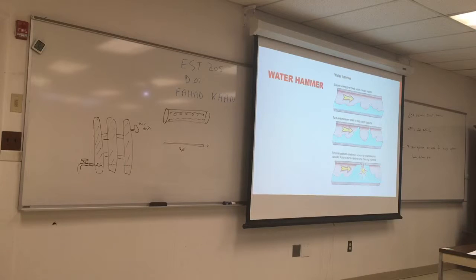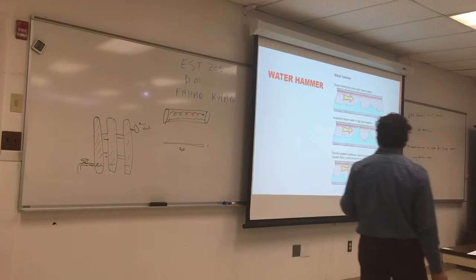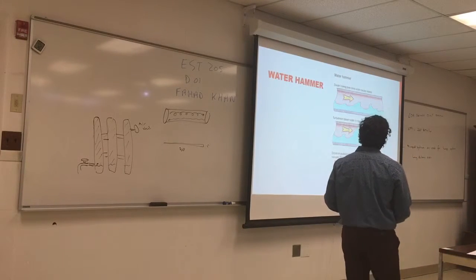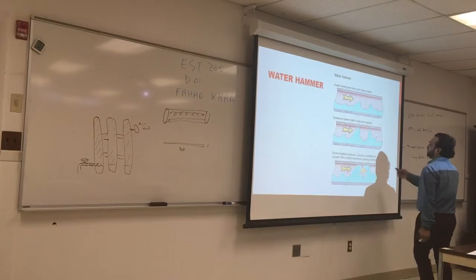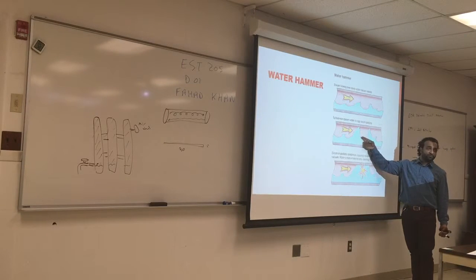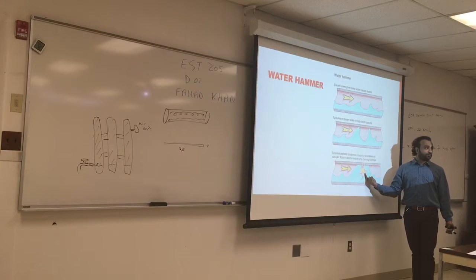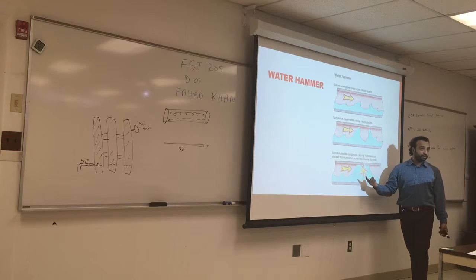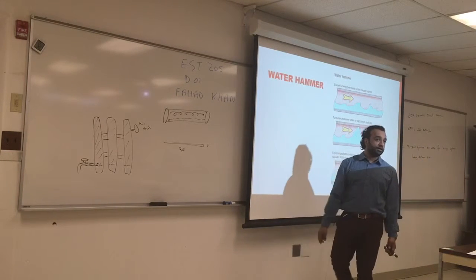Some of them have adjustable legs where you can unscrew them and raise them up from one side so they will tilt to the other side. So you get the water to flow. When you don't have the proper tilt, this is what happens. The water runs very quickly, and you will have a steam pocket. This pocket, over time, will be pressurized, and eventually the steam will try to find a way out, and it will cause this strong noise of water hammering.